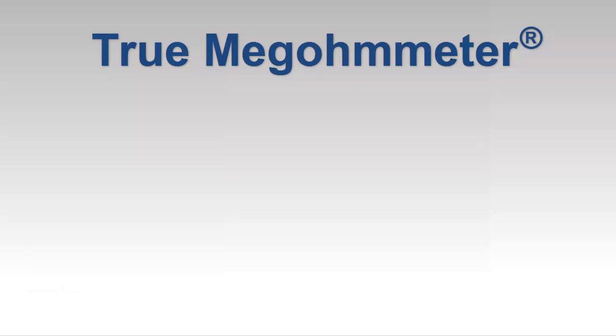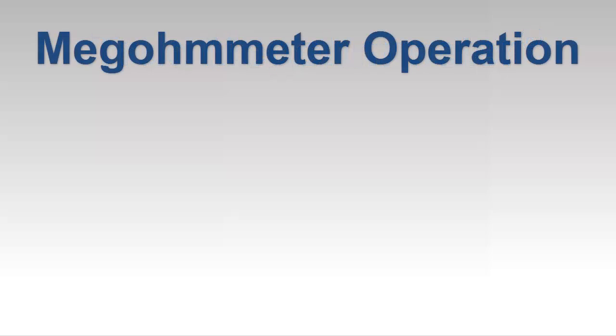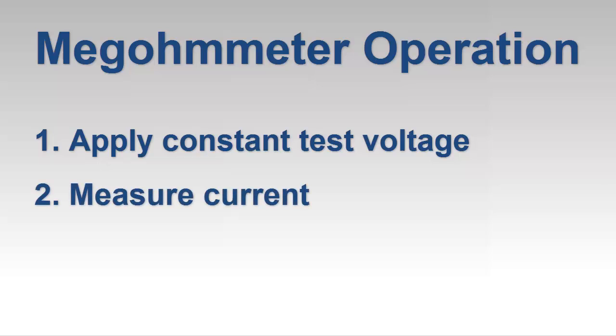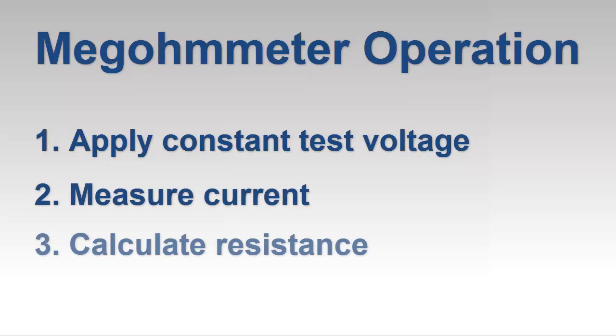Another term unique to AEMC is True Megohmmeter. To understand its meaning, consider the general principle behind how megohmmeters operate. These instruments apply a constant voltage to the insulation under test, measure leakage current on the conductor, and then calculate and display resistance using Ohm's law.